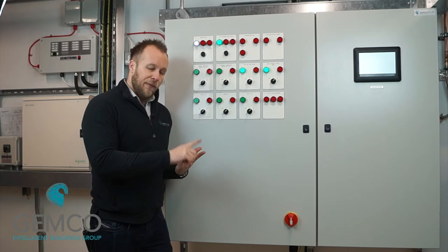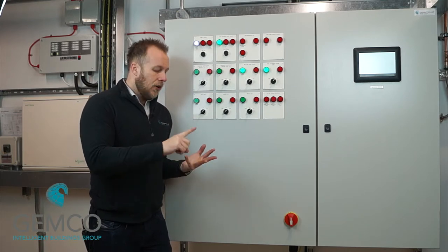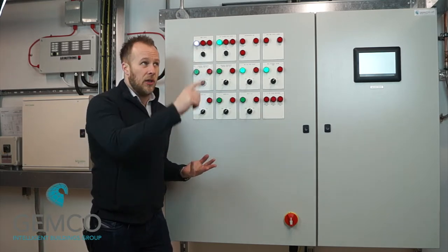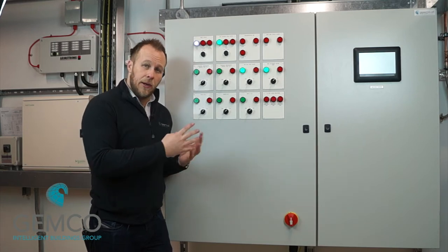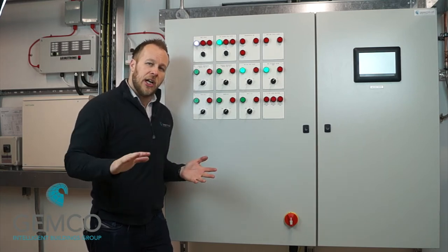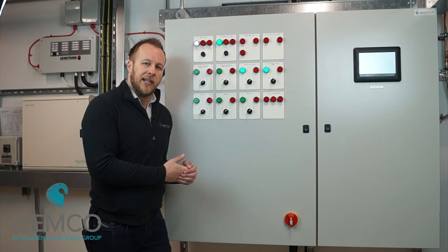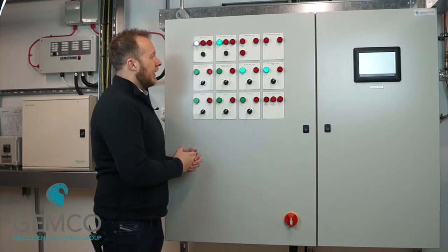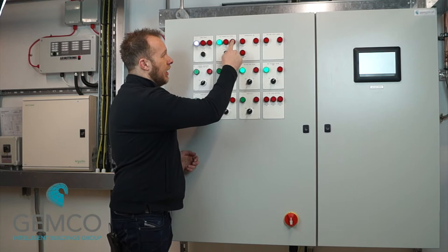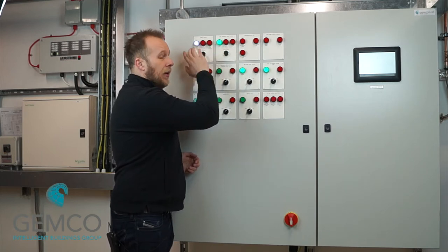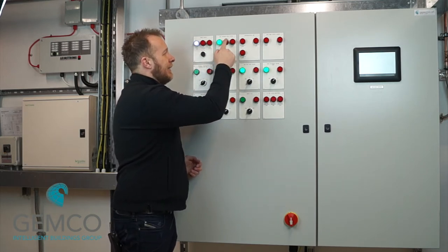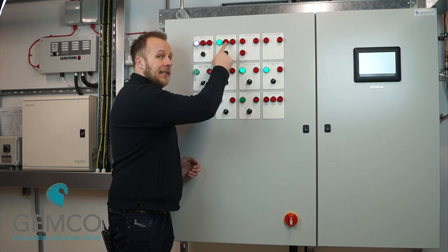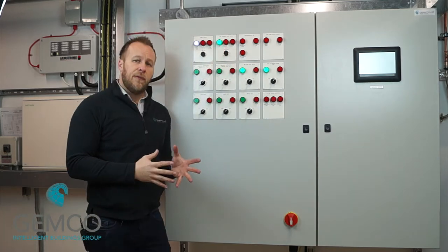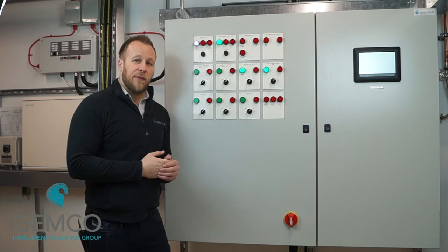So if you've got a fire, a gas leak, or someone's hit the knockoff button, or heat melting the link above the boiler, we're going to shut the gas off. Last thing we want to do is bring more gas into the building. So we shut the gas off, and what will happen is you'll get a closed light lit, the open light will go out, and you'll also have a gas safety circuit failed light lit as well. The whole time there's a fault, you're going to have a gas safety circuit failed light.